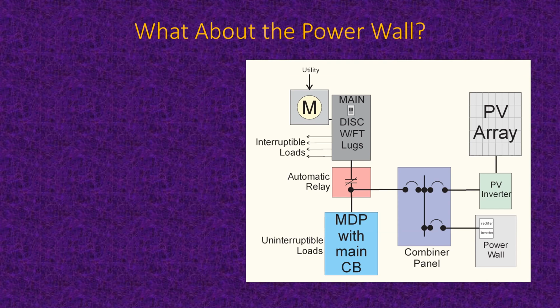I mean, we do a lot of systems that have generator plus PV, but the PV always has to be tied in on the line side of the generator so that it can be disconnected. The PV inverter power has to be disconnected from whatever the generator loads are being fed. Otherwise, it could be an unhappy day for the generator.